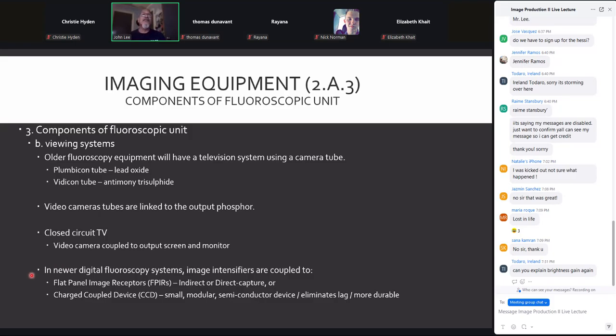Our newer digital systems: image intensifiers can be coupled to flat panel image receptors, but it's not a good thing, because the image intensifier's maximum output is 5 cm, but we could just use a smaller flat panel. But the preferred method would be to use a charge coupled device, a CCD or a CMOS type chip, because they are much, much smaller. It does eliminate lag. They are more durable. They're modular, so they're easily replaceable. Low cost as well.